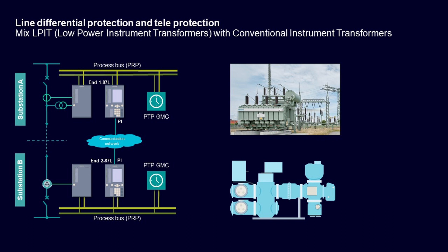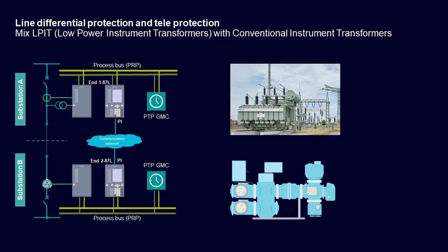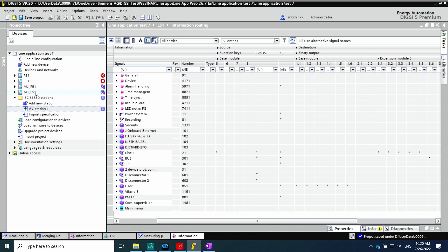We open DiGSI software to configure the SIPROTEC 5 devices and the merging unit. First, we have a look at the merging units. In one merging unit we have a low power instrument transformer (LPIT) from Siemens Energy, and the second merging unit is connected to a conventional instrument transformer. I will start with the merging unit connected to the LPIT, which is called LS1.